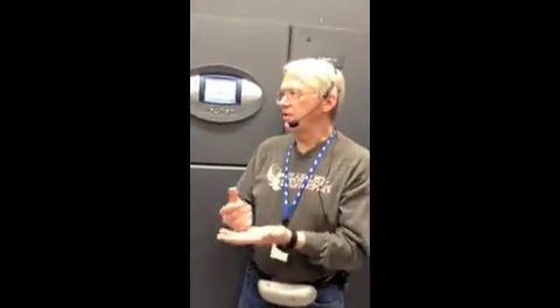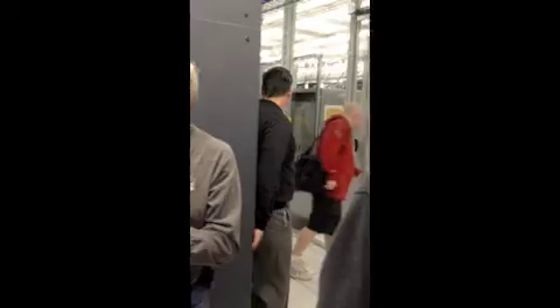Okay, we're going to move on now outside. We're going to see the infrastructure for the cooling and power. This is stuff you normally never get to see in a data center. So we're going to visit the pump room where you can see the primary and secondary cooling loops. We're going to see the chiller room. We will move on around. We will see the evaporative coolers outside, and then we'll finish with a stop at the main power plant. And there we bring in 13.2 kilovolts from the outside. And you've been cautioned not to touch anything, but that applies here. If you want to touch something in the power plant, my one rule is you've got to tell me first so I can get it on video and post it on YouTube. Okay, let's go.